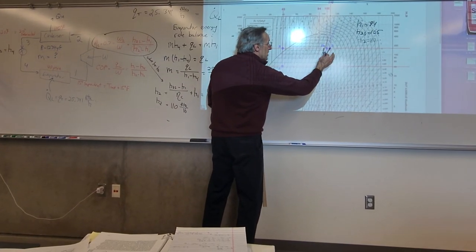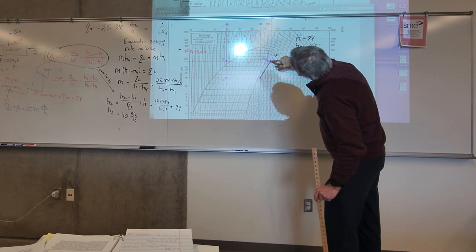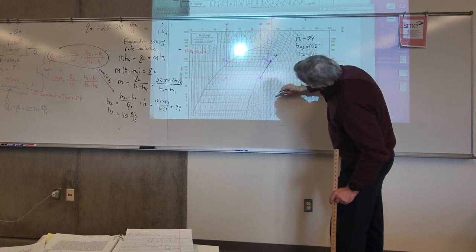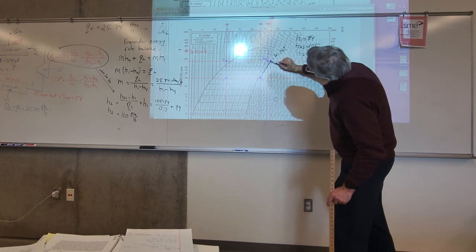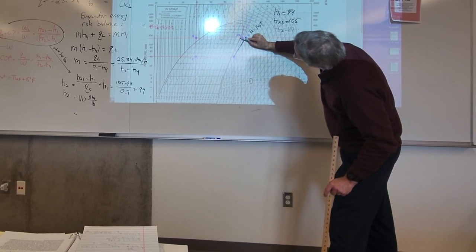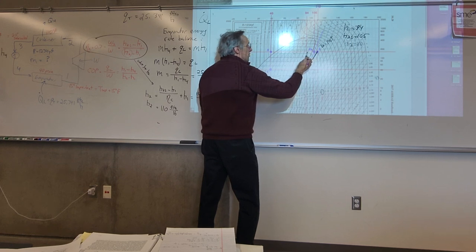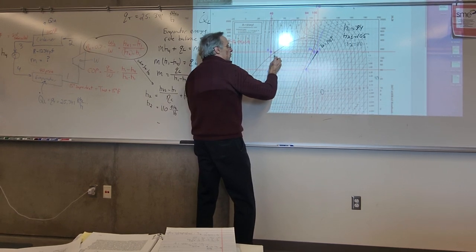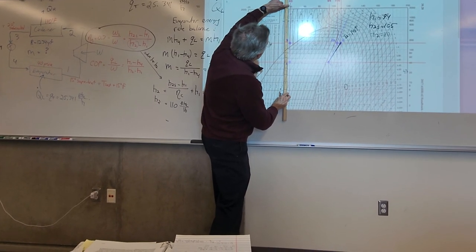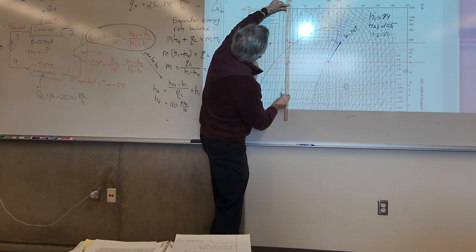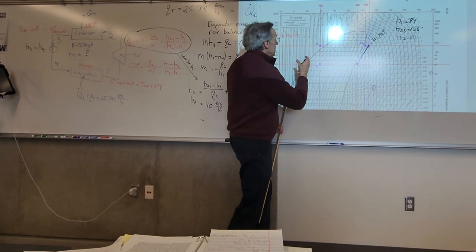All right, now we de-superheat from 2 to saturation, so we're going to drop in temperature. Looks like T2 is right on the 140. So we're going to cool from 140 to saturation, which is 110. Once we're at 110, we begin to condense the refrigerant, and we go all the way until we get to state 3, subcooled liquid state, and then we can get the enthalpy there by drawing a straight line to the horizontal and reading off our enthalpy. Very convenient, it lines up right at 40. And H4 equals H3, so that's handy.